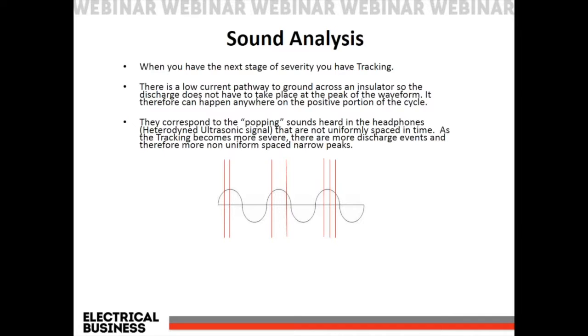So when we have the next stage of tracking, just to summarize here, there's a low current pathway to ground across an insulator, so that discharge does not have to take place at the peak of the waveform. It therefore can happen anywhere on the positive portion of the cycle. They correspond to that popping noise that we were hearing. That's exactly what we're hearing. And they end up becoming more non-uniform and very narrow peaks. And those narrow peaks and non-uniform patterns that we see are a clear indication that this is tracking.